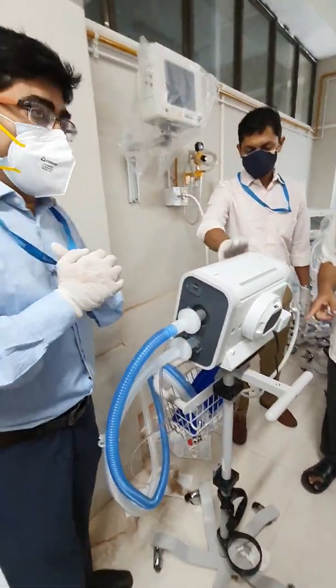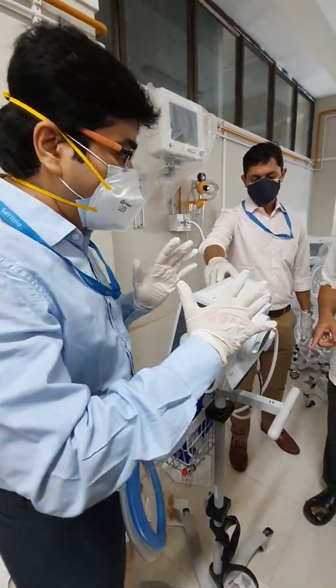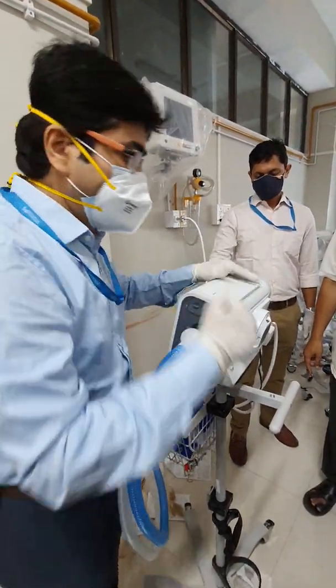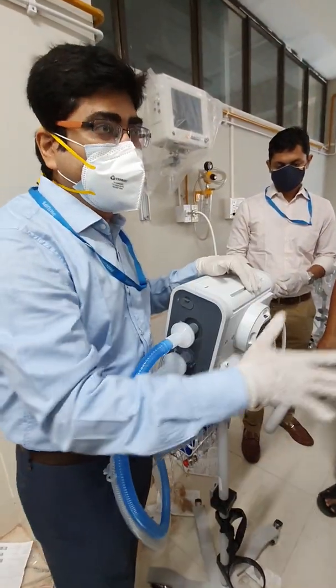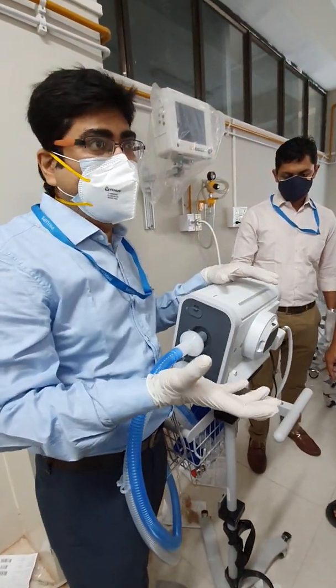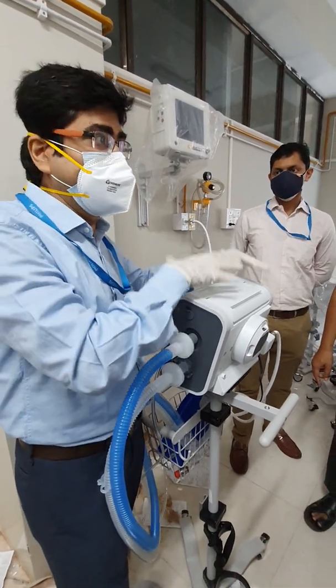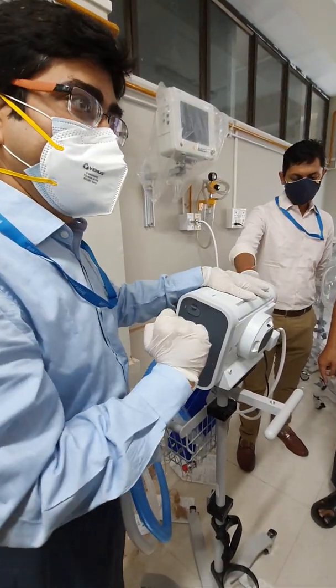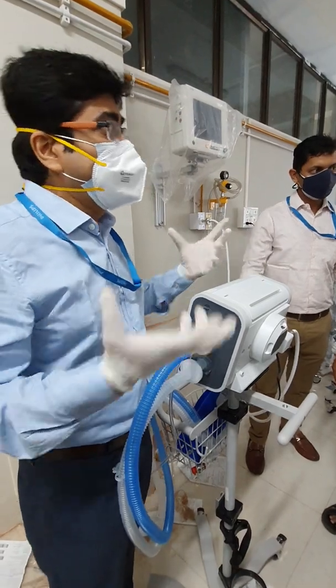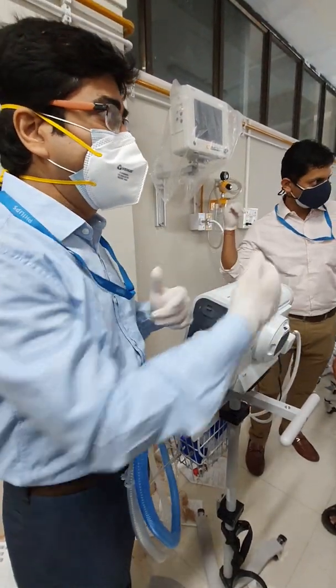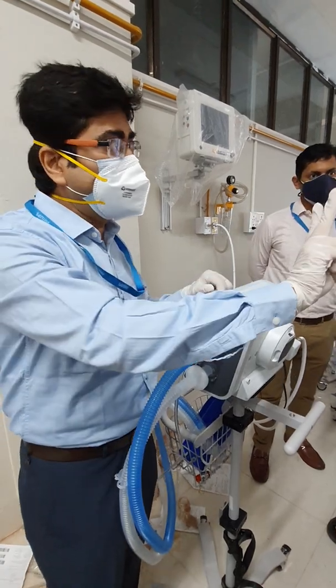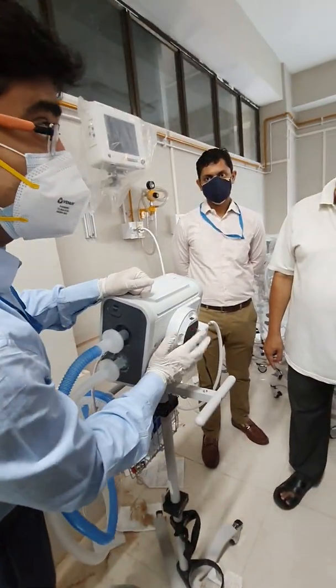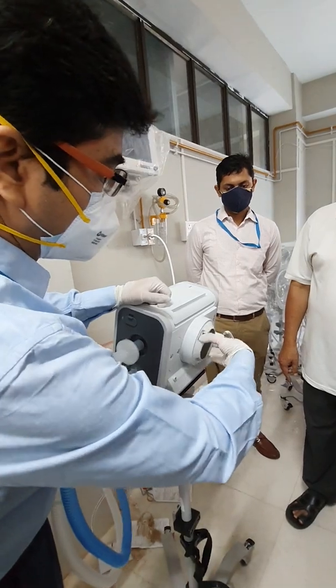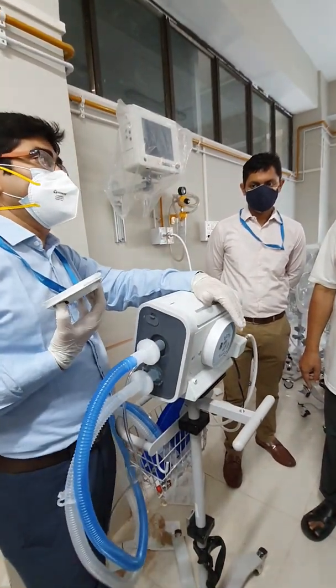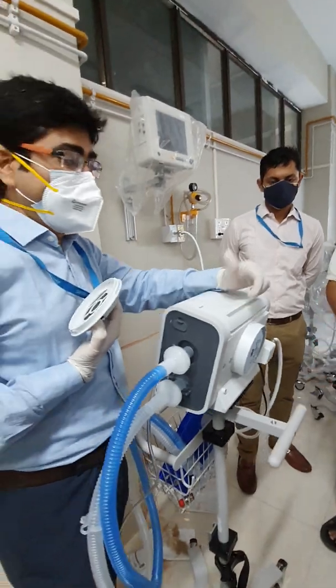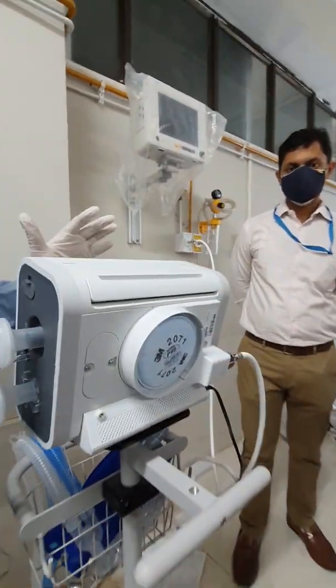So, okay. I will start from the back side of the ventilator. As I said, this ventilator has an internal air source, a compressed air source. But the air it collects is taken from the atmosphere only, so the air must be purified before taking it inside the machine. So we have a two-stage filter. One is this, and then if I open it, there is one HEPA filter. So a two-stage filter is there, and then the air goes inside pathogen free.